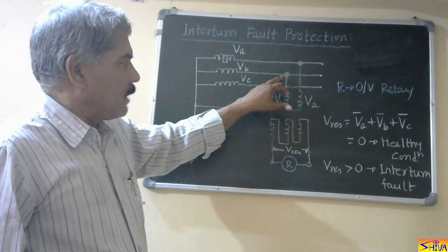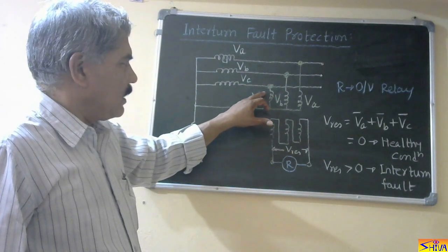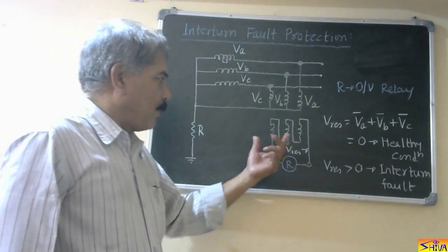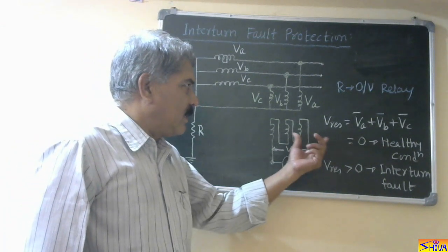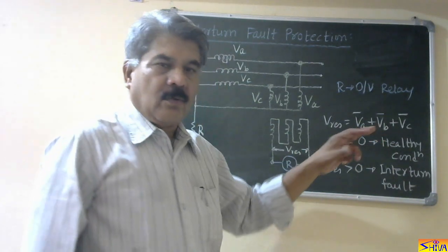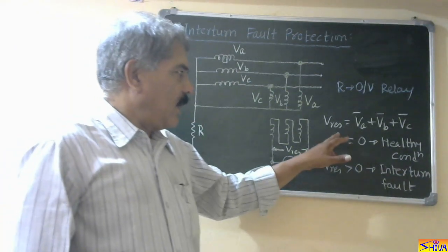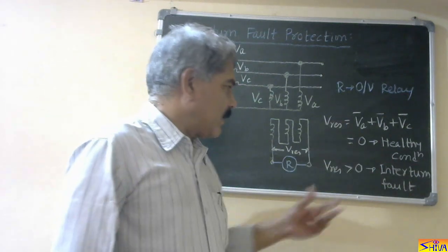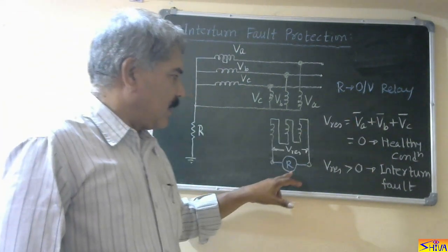Vb is the voltage measured between phase B and the neutral point. Similarly, Vc is measured between phase C and the neutral point. This is an open delta, so across this open delta, let us denote the voltage as V-residual. It will be Va plus Vb plus Vc. Under balanced conditions — that is when there is no fault — Va plus Vb plus Vc will be zero. That is the normal or healthy condition. Across this open delta, we connect an over-voltage relay, that is relay R.